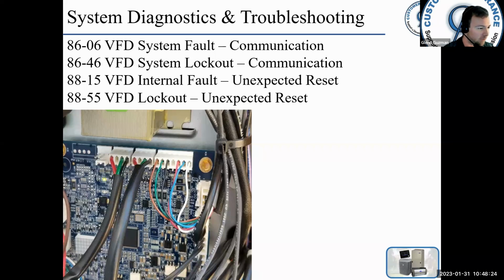to tell us. Okay, so communication between the VFD and the PCM is happening constantly. If it does not happen for a continuous 15 seconds, then you get the 8606. If you have 3 occurrences within 15 minutes, then you get the 8646, which gives you a 1-hour lockout. When 8606 is set, the VFD shuts down the compressor and the fan and will reinitialize, attempting to reestablish communication between the VFD and the PCM.